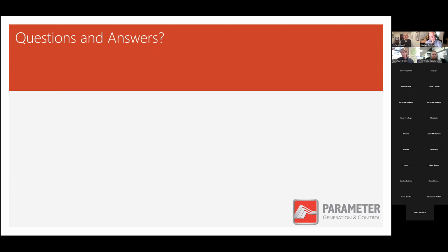So we do offer validation services. In my experience, the validations most often involve 16 sensors, 16 temperature sensors. I don't believe there are as many humidity sensors.